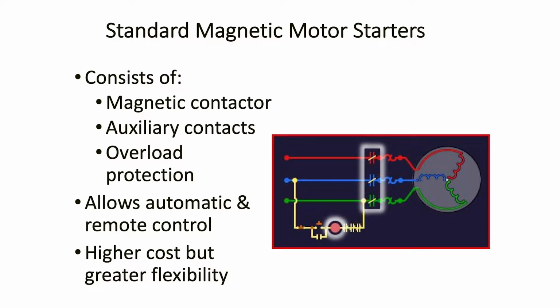So what do we need to think about? Maybe doing a better job of relaying to some of those younger folks why we care about these rules and what can happen. So typically a standard magnetic motor starter is going to have a starter, going to have some overload relays, and if we use a start-stop station, push buttons, we understand how we wired it up, how that system works. We've done that forever.